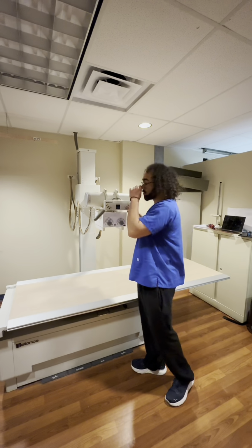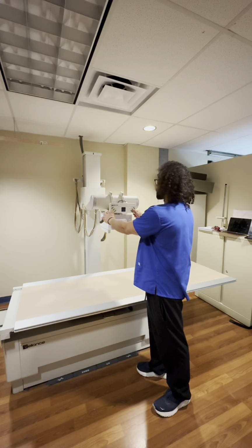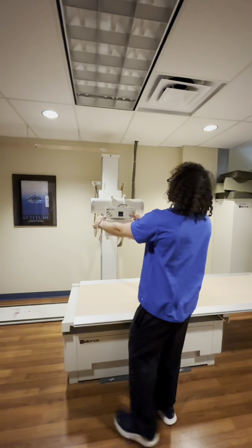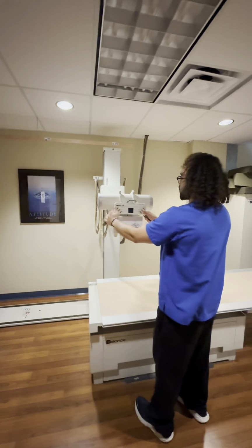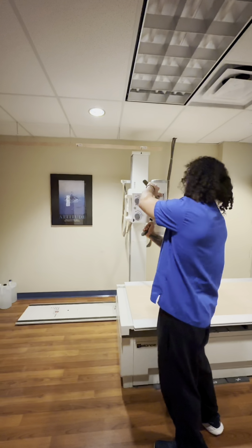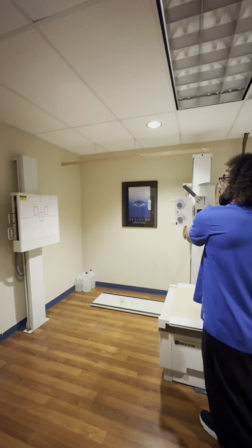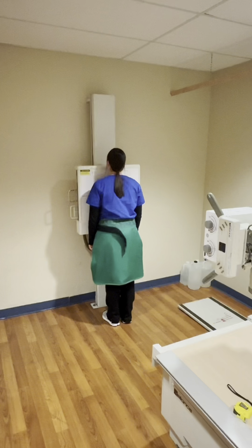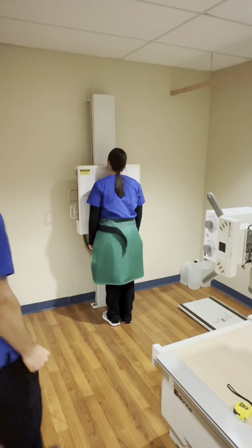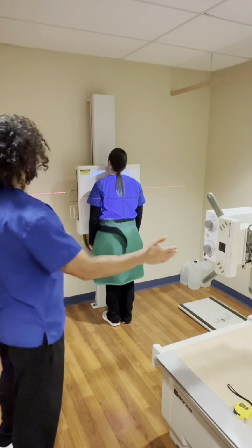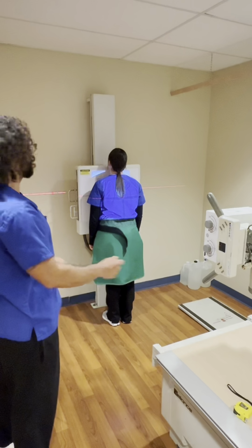You want to align your bucky to your tube here. Since we're doing a chest, we're going to do a 72 SID. So we're lining up to the 72 up there. And obviously you want a horizontal beam. Then you also want to make sure that you're detented transversely as well. All right, so before you position your patient, you're going to have them shielded, of course.